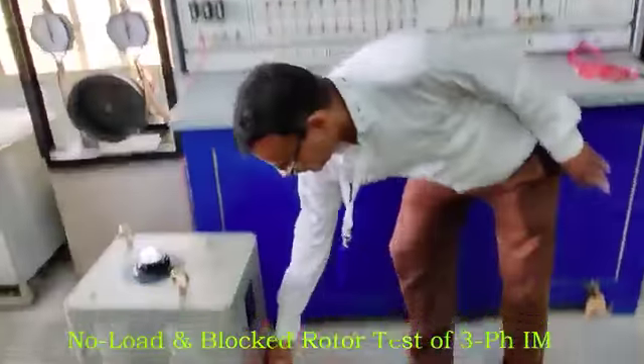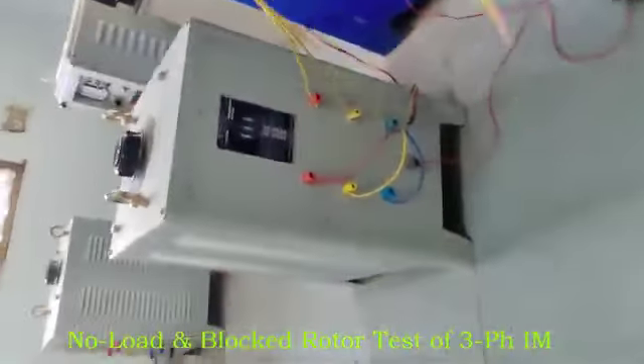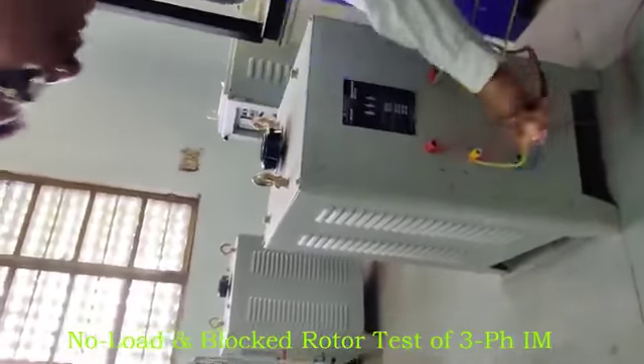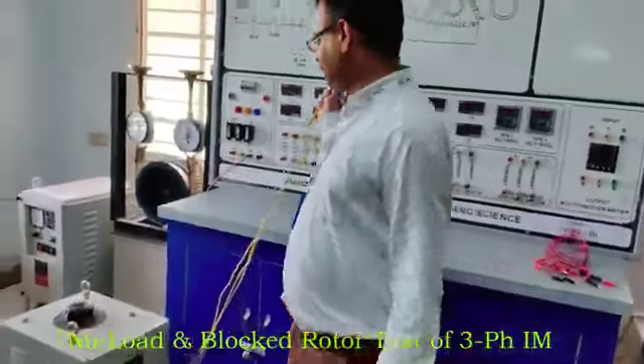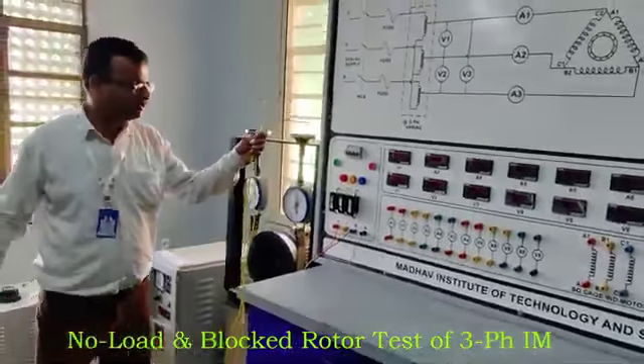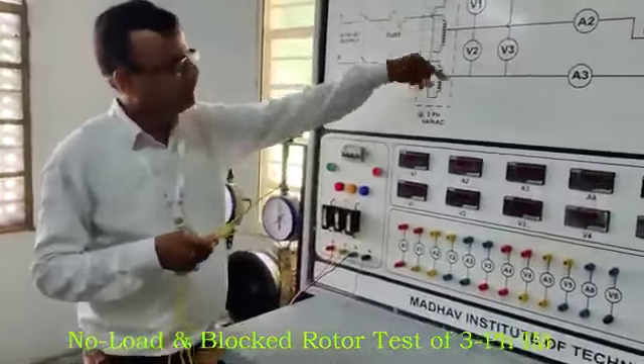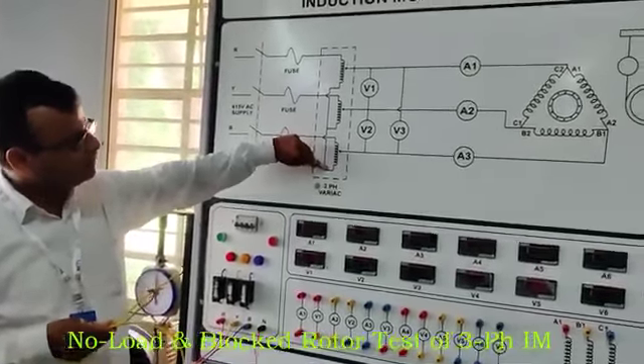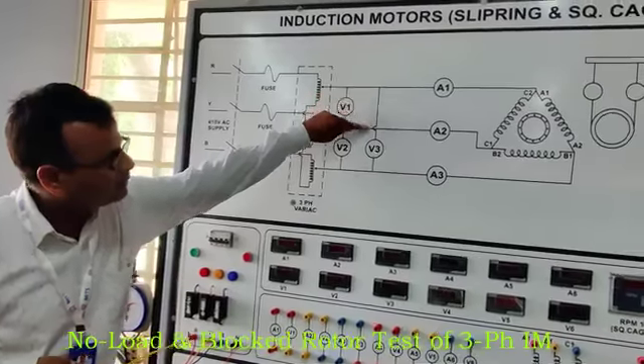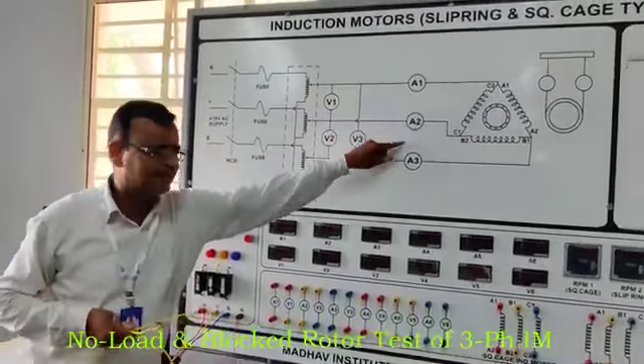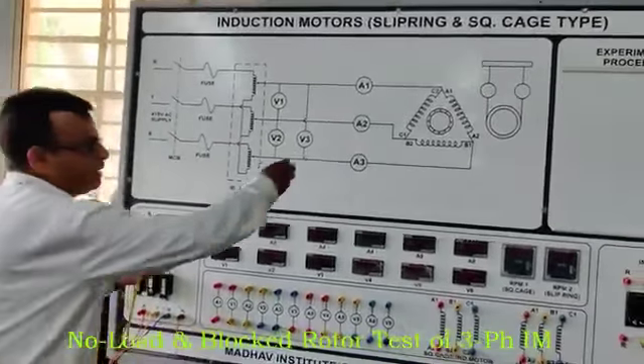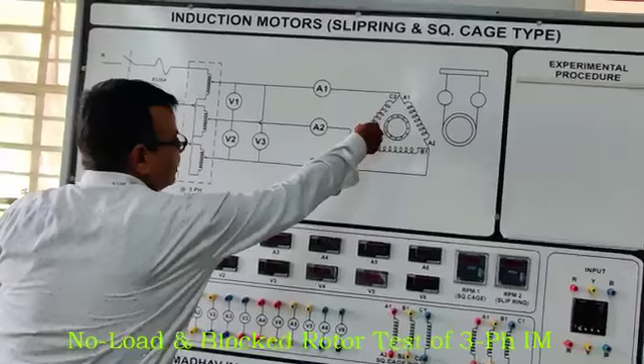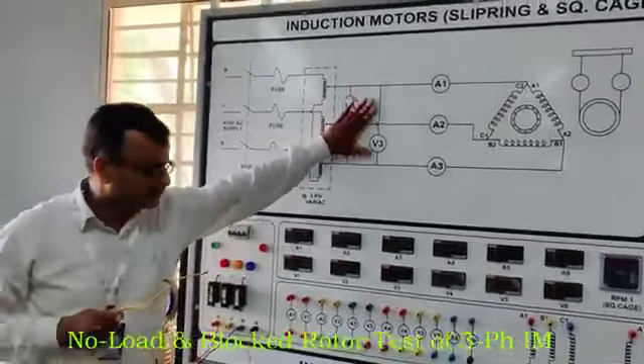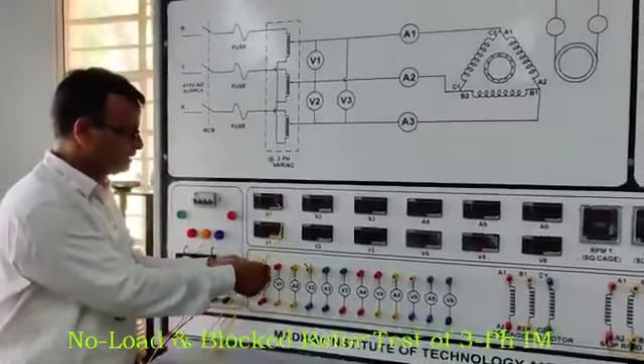So this is the autotransformer, and we will take connecting leads here. This is the input terminal. As you know, the input is a constant 415 volts, and these are the output terminals. The output means the variable output, which we will connect according to this diagram. See that these are the autotransformer terminals. There are 3 line terminals, 1, 2, 3. In these 3 lines, the 3 ammeters are connected in series, and these terminals go to the 3-phase squirrel cage induction motor. So first of all, we connect this portion of the circuit, and this one is the ammeter here in series like this.